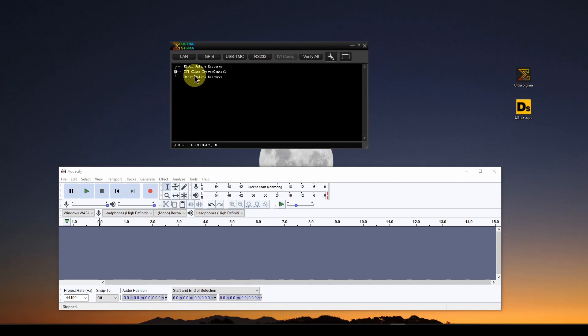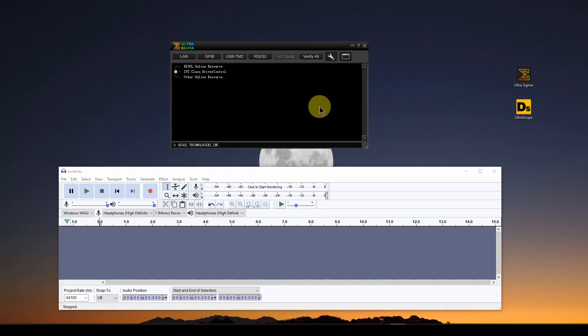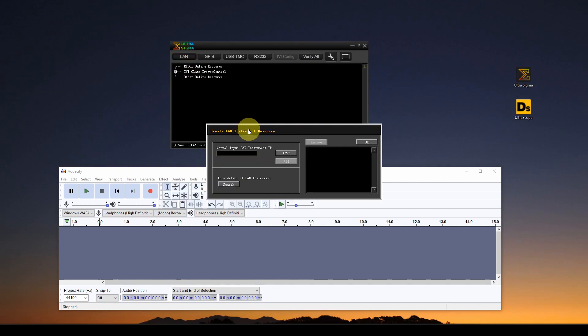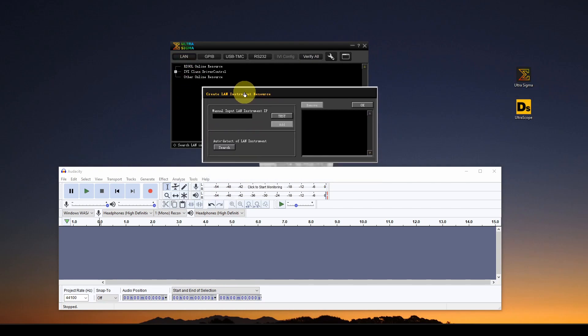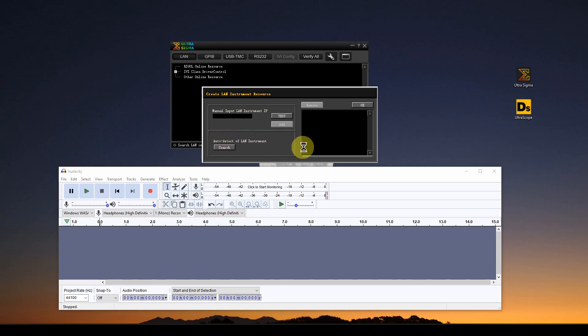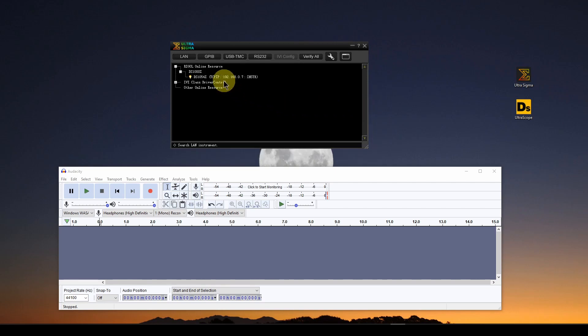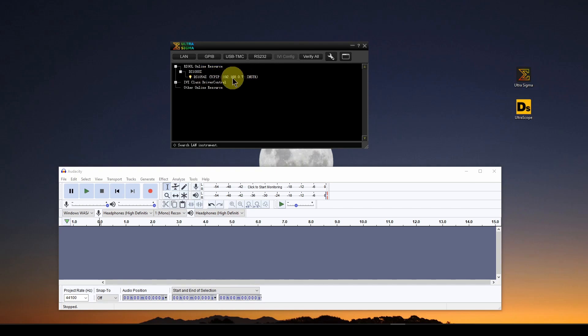You can see it's got a list of devices available. There's nothing right now, but you've got a LAN connection, GPIB, USB, RS-232, and so on. Since we're connected via LAN, I'm going to click on LAN, and it's going to give me another window to identify and create this instrument resource. So I go down here to auto-detect of LAN instrument and hit search, and there it is. It found my DS-1054Z scope. So now I hit OK, and you can see it populates up here on the list, DS-1000Z, and the specific device is DS-1054Z, and here's the TCP IP address, and it's an instrument. So we're good to go. UltraSigma is working.